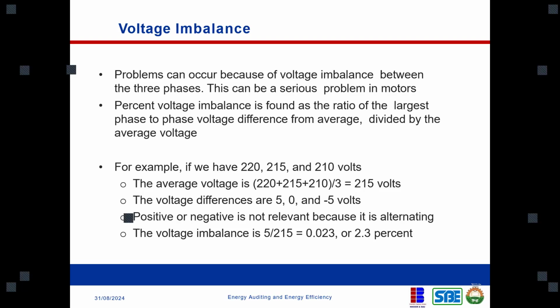Mind you, if we had minus 10, for example, assuming this minus 5 is minus 10, then the highest deviation will be that minus 10. Like I said, the negative is irrelevant. It will be that 10. But in this case, we have 5, and we also have minus 5. So the highest here is 5. So we divide the 5 by the average, which is 215 volts, and we get 0.023, or 2.3%. Now, the voltage imbalance in this system is 2.3%.